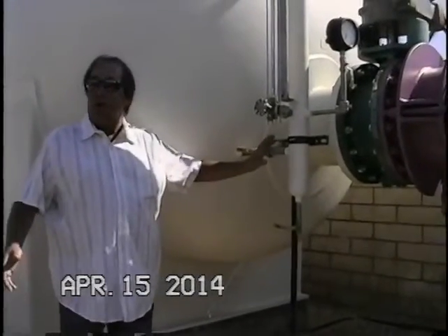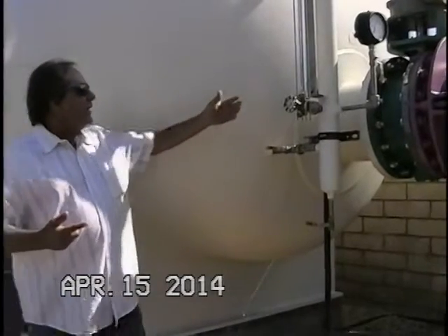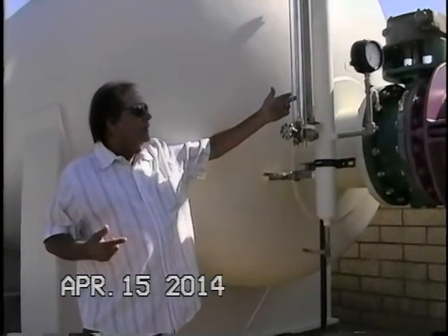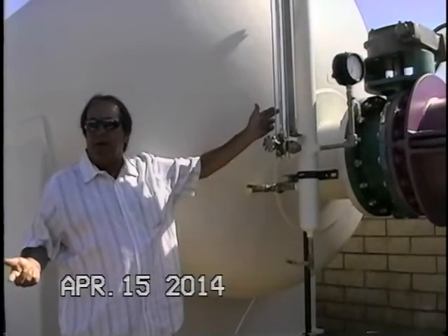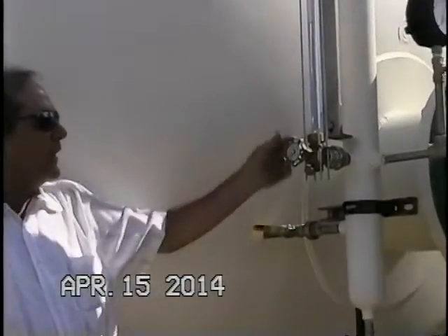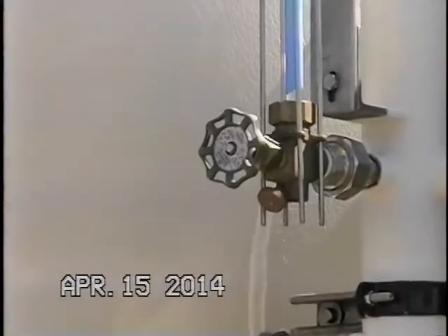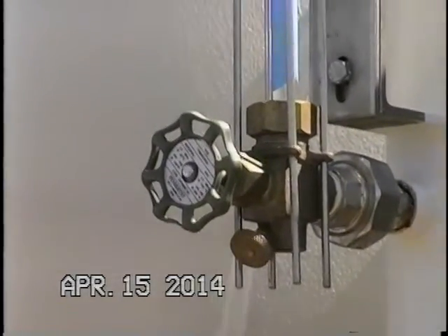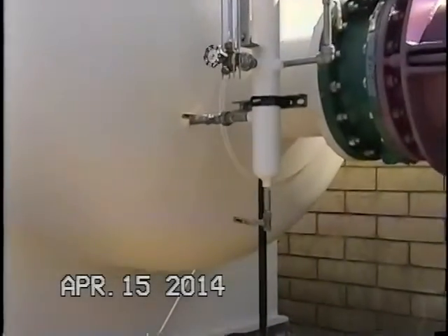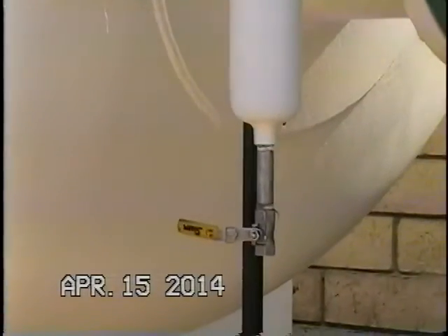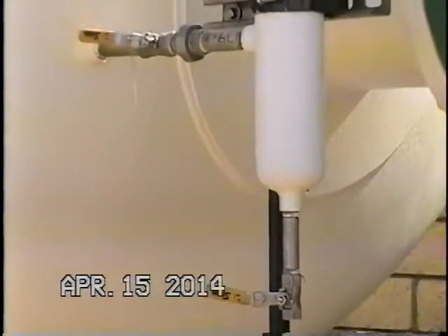Typically, it's not a bad idea, especially in a reclaimed water system, because it is a stilling well and you don't get much flow in and out. You're pretty chlorinated here, so you shouldn't see much buildup in the sight glass. There is a drain valve here that you can open up that will clean the sight glass out a little bit. The other thing you can do on the probe well is just open up the valve and flush it out every so often, once a month, once every 2 months. The system doesn't require maintenance, but little things like that would certainly help.